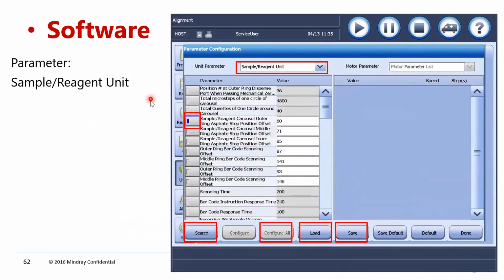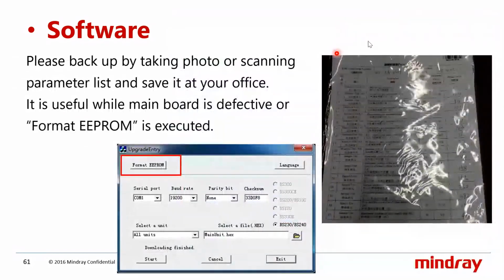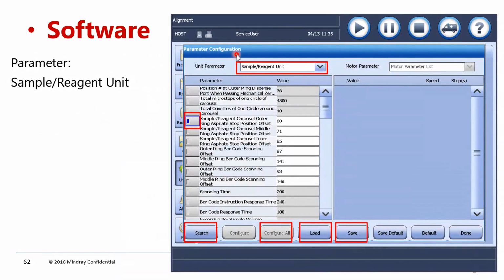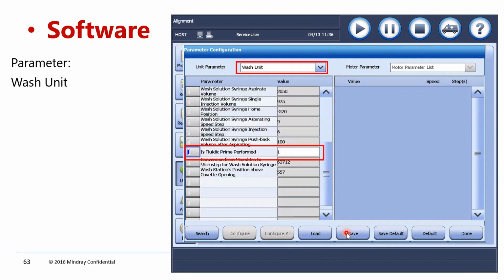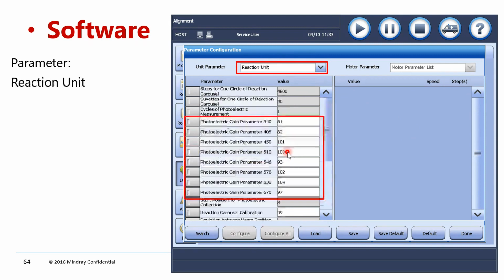So the sheet values we are entering here in the parameter configuration. You can select module-wise. This is the sample and reagent unit, so you have to enter all these values if they deviate from the sheet. At the time of installation, you observe whether the instrument has the same values or not. If not, you need to change these values. And this is about the wash unit, such as whether wash fluidic prime is performed 1 time. These are the values for the reaction unit, such as photoelectric gain. These values are normally given by the factory, and you have to enter them.